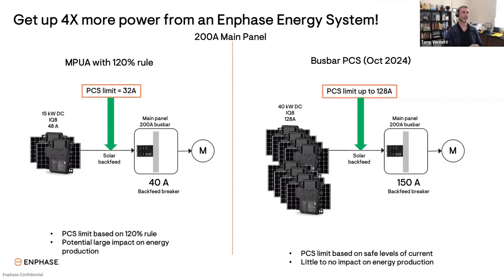And one last example here. This is a solar only system installed on a 200 amp main panel. With the 120% rule, there's a limit of 32 amps of backfeed current. With Busbar PCS on this 200 amp panel, the backfeed current can be as high as 128 amps, which is of course a massive PV system. So the point here is a lot more flexibility.